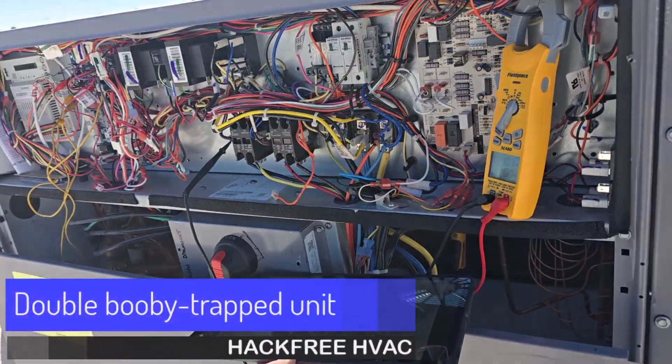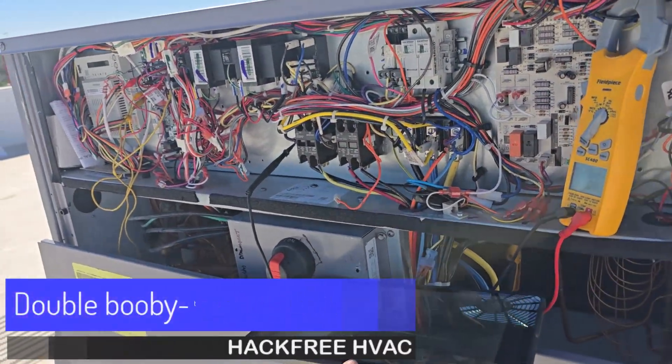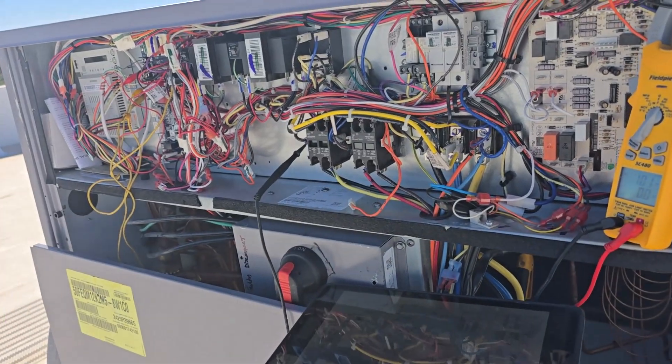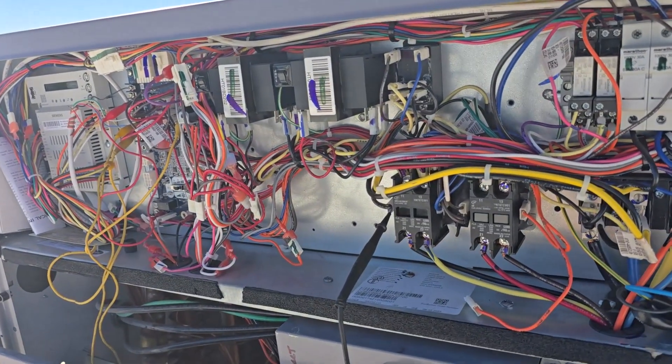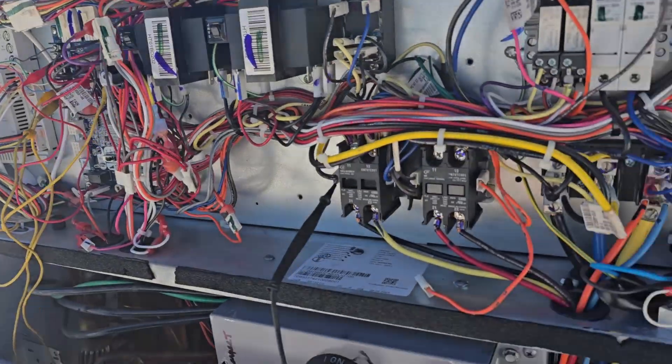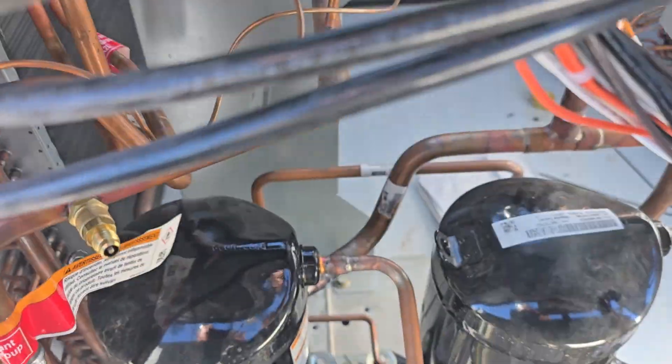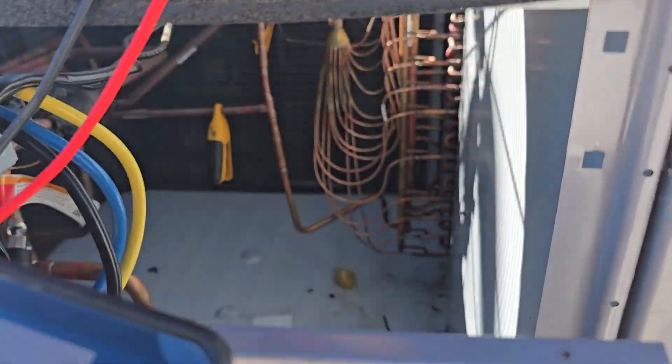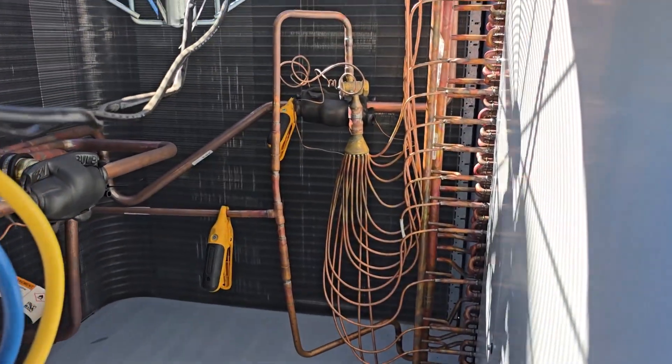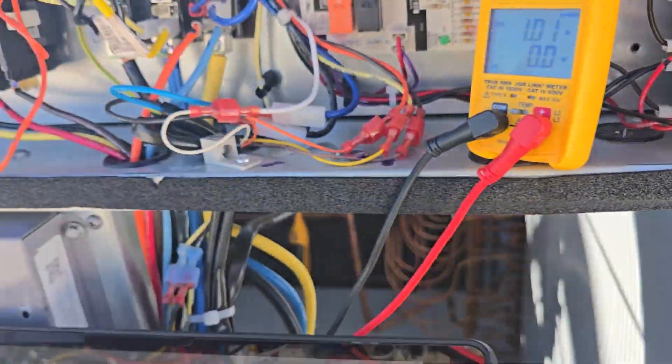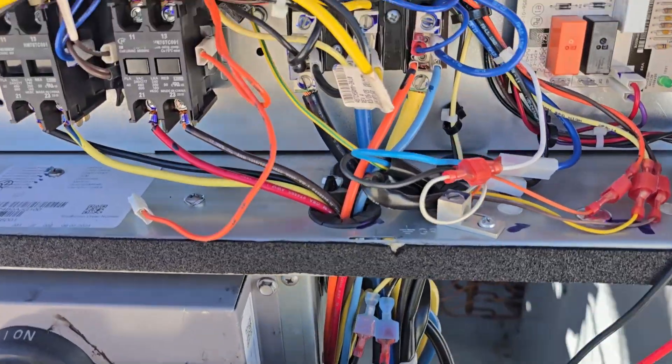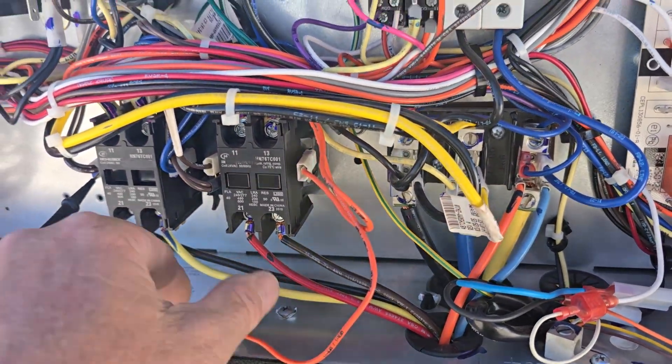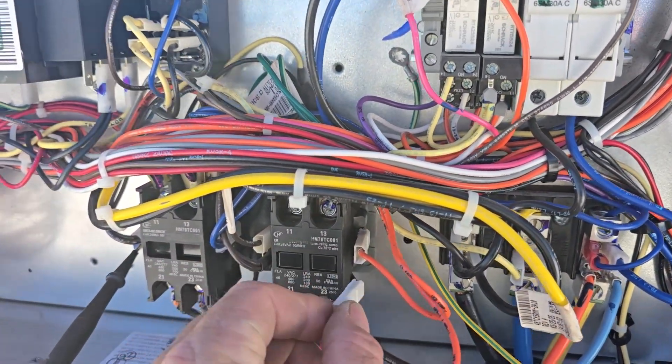I'm at a brand new unit that was icing up soon after install. Found another little weird factory booby trap here. Basically it's a two-stage tandem 10-ton Carrier unit. Cap feeders with the TXVs were all frosted up and everything, but what I found here is that the factory booby-trapped it by sticking this orange wire on here to the contactor.